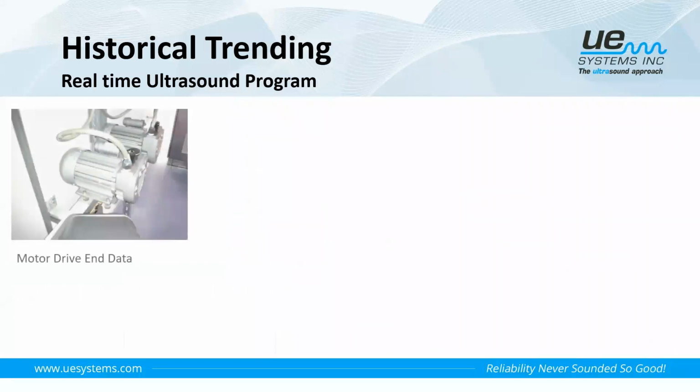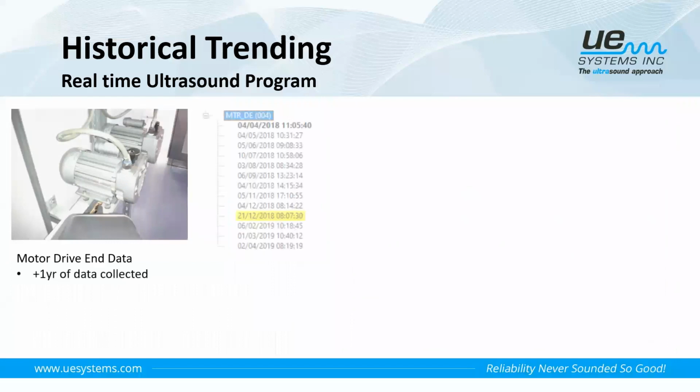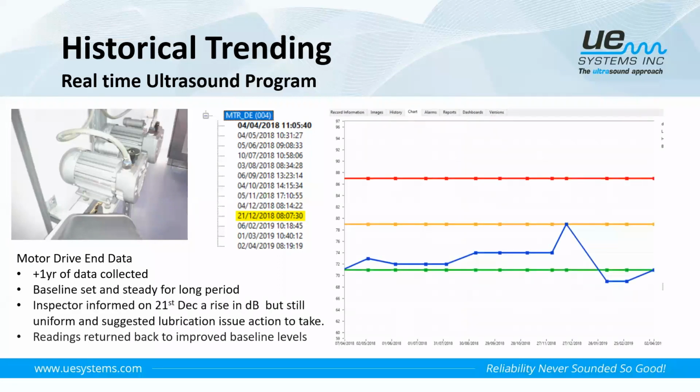With the same program, we had another motor drive end bearing being inspected on this site. We had another year's worth of data, where we can now see a little yellow highlight there, a low level alarm being indicated. So the baselines were set, and as I said to you, when you have a good baseline, it will stay steady for a long period of time. But as we can see, it started to climb slightly, and then all of a sudden we see an increase to 8 decibels above the baseline, which indicates a low level alarm and some lubrication may be required. The inspector on this site told me they discovered this low level alarm, and they did some rectification work. And as we can see afterwards, the baseline has returned back to a low level again, and we're running nice and smoothly. Great way of using historical trending.